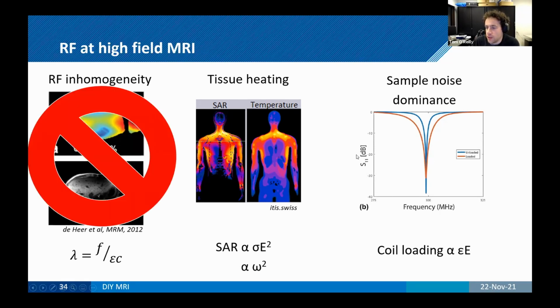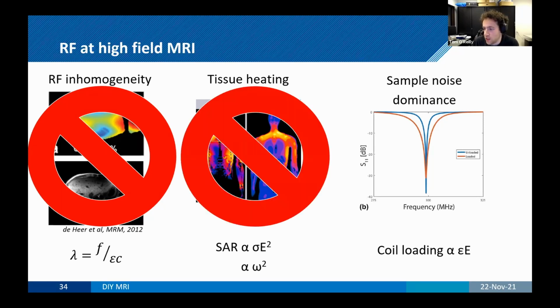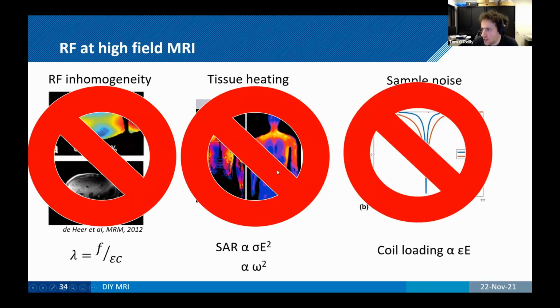So at low field, this is not true because our wavelength is 150 meters. Tissue heating is not an issue because it scales with omega squared, and we're, let's say, 100 times lower in magnetic field strength. And sample loading is also really not a factor at low field, again, because of that scaling with the electric field.